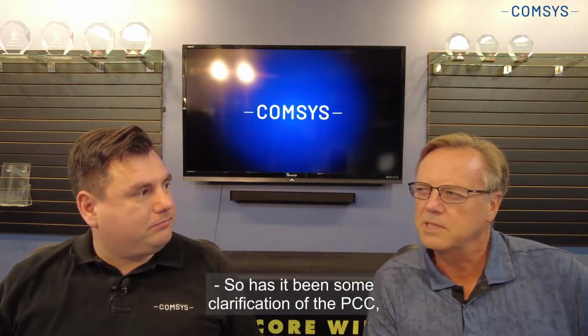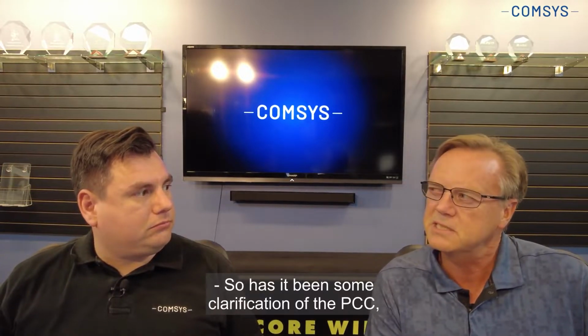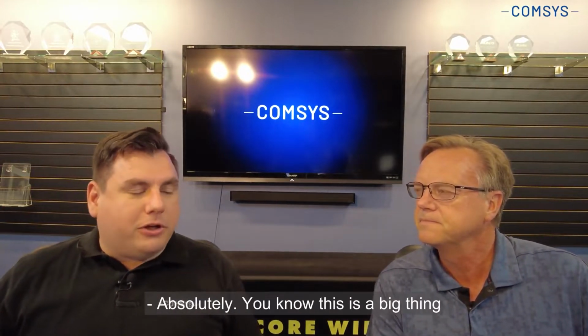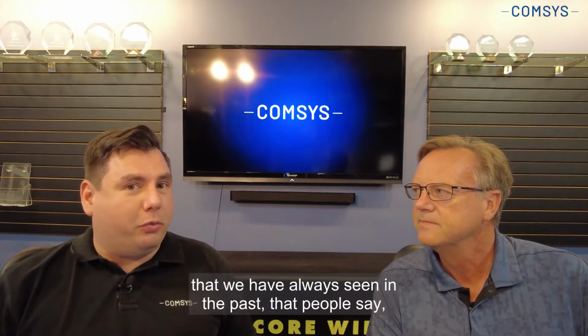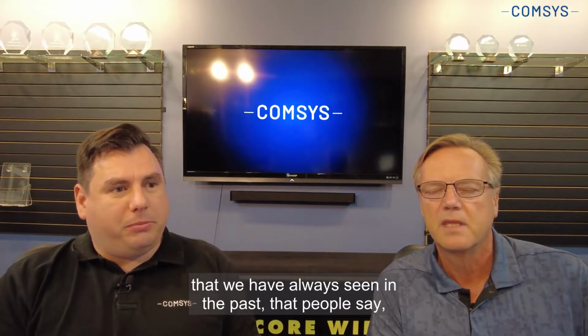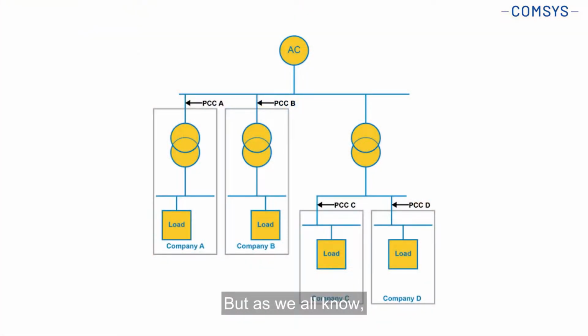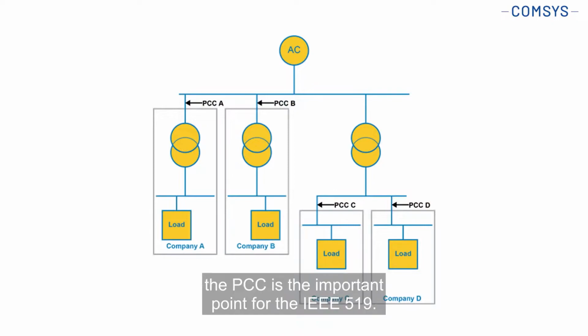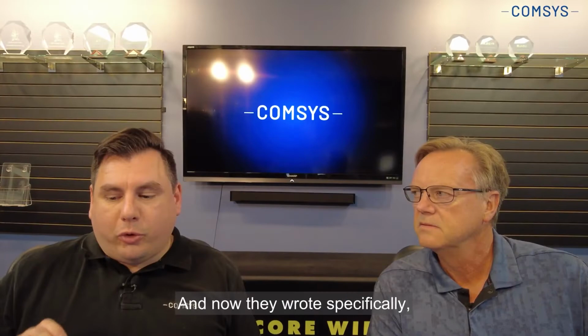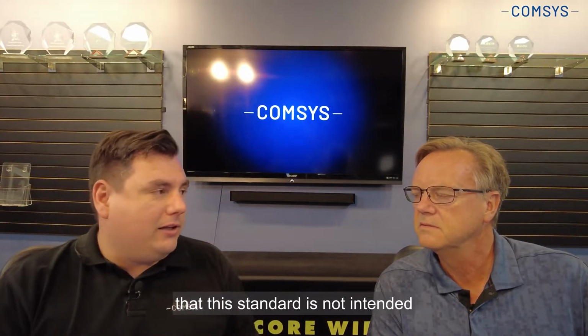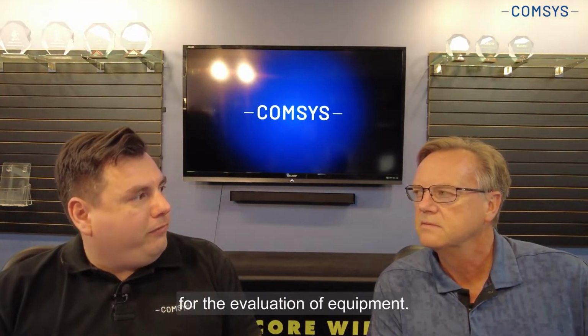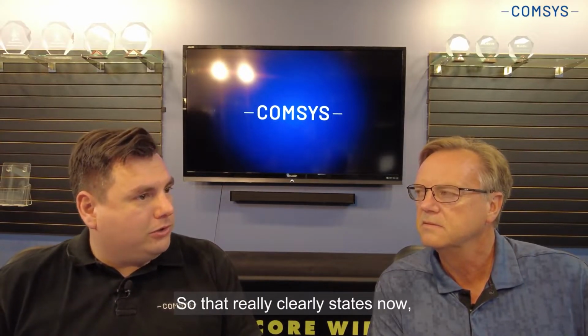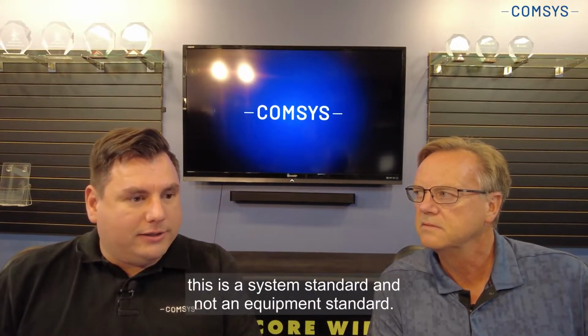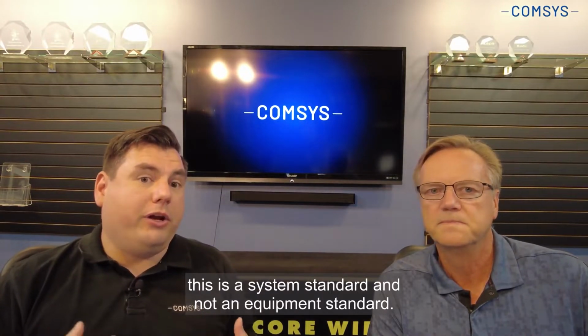Has there been some clarification of the PCC, the point of common coupling? Absolutely. This is a big thing that we have always seen in the past, that people say, hey, I need to have my IEEE 519 on this drive. But as we all know, the PCC is the important point for IEEE 519. Now they wrote specifically that this standard is not intended for the evaluation of equipment. So that clearly states that this is a system standard and not an equipment standard.